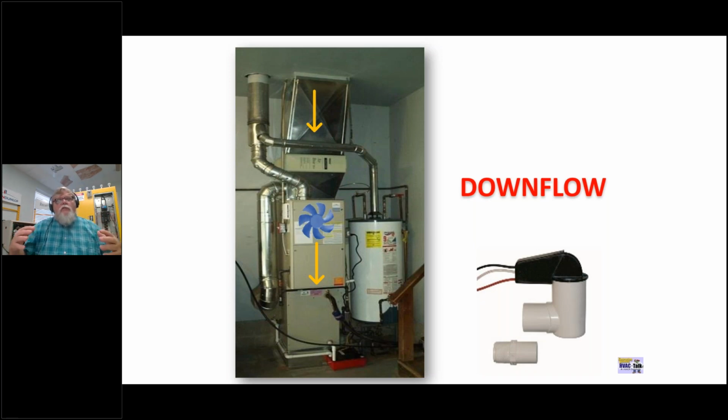As a service tech, I learned a long time ago, if I can give them fan operation inside the house, even though it's not cool air, if I can give them some air in the house, they tend to let me wait till tomorrow morning to come out there and make the repair. So that way I don't have to get up in the middle of the night and deal with something like this. So all I ever do is use the float switch to shut off the outdoor unit, the condensing unit, or a heat pump, I'd be shutting off the outdoor unit.